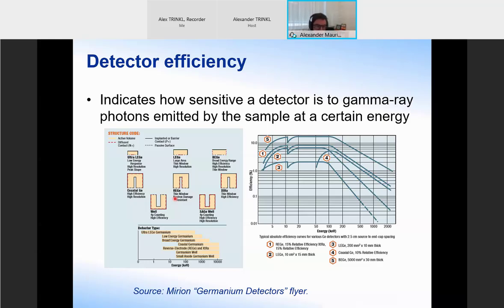Low energy photons will tend to be absorbed quite quickly, statistically. Higher energy photons will tend to travel larger distances. So you get these kinds of efficiency curves. You see that N-type detectors, which is curve number 1 here, have a better efficiency at low energies than the P-type detector, which is number 4 here.